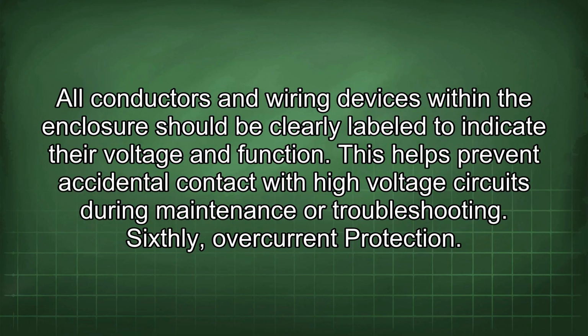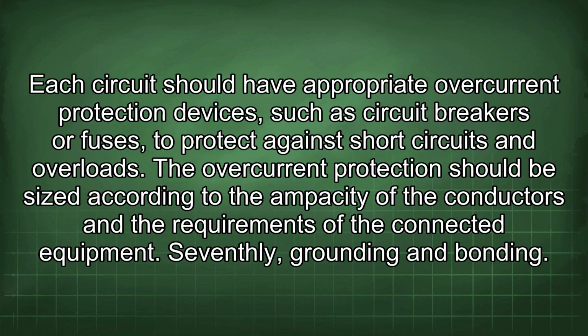All conductors and wiring devices within the enclosure should be clearly labeled to indicate their voltage and function. This helps prevent accidental contact with high voltage circuits during maintenance or troubleshooting. Sixthly, overcurrent protection. Each circuit should have appropriate overcurrent protection devices, such as circuit breakers or fuses, to protect against short circuits and overloads. The overcurrent protection should be sized according to the ampacity of the conductors and the requirements of the connected equipment. Seventhly, grounding and bonding.